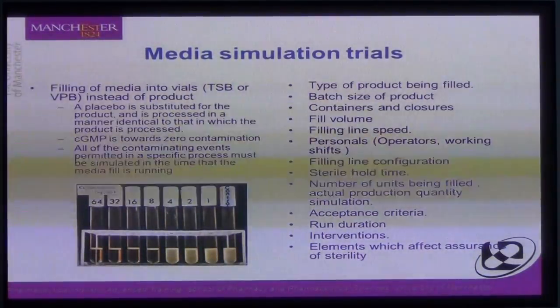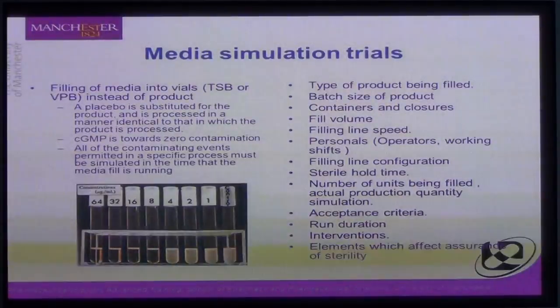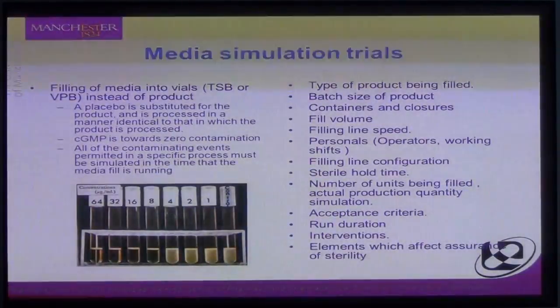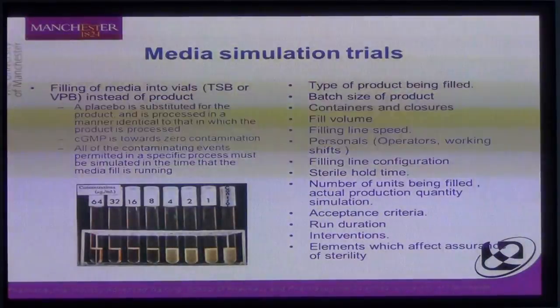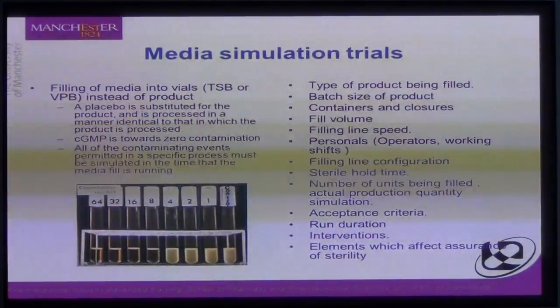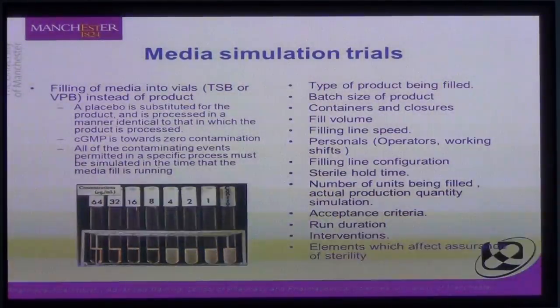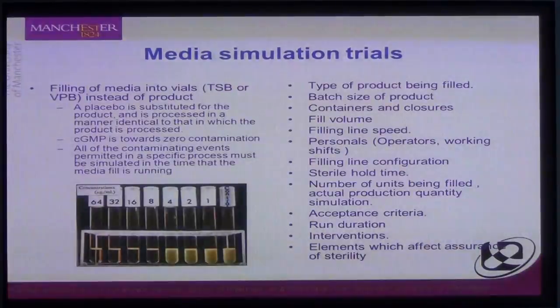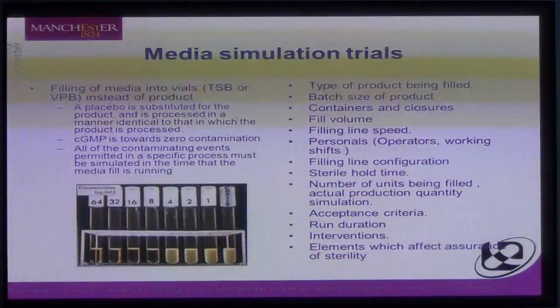In constructing a media filling trial protocol, there are many factors to consider: the type of product being filled, the batch size, the containers and closures used, the fill volume, the filling line speed, the way people act, the filling line configuration, whether we pause the process, how many units to fill, the acceptance criteria — which these days is no contaminated units — how long the media trial will last, and the number and frequency of interventions. Putting together a media trial protocol is a complex activity, and the course module has considerable text devoted to this important subject.